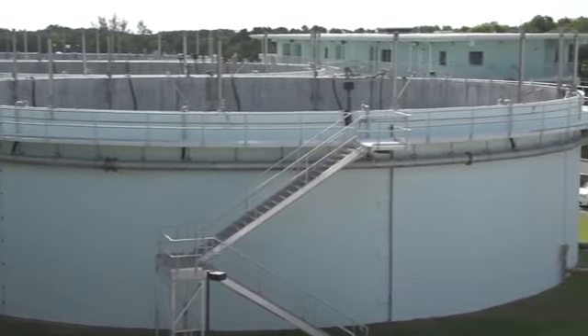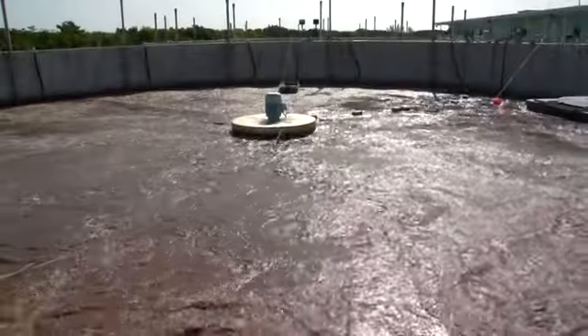We are now currently treating an average of a million gallons a day. The benefit of a true SBR is the batch process — the sequence. On one of the tanks, the influent valve closes and you only treat a certain volume of water, versus a plant that's not a true SBR, which is always accepting flow. It's really hard to dial a plant in for nutrient removal on a plant that doesn't treat just a certain volume at any given time.